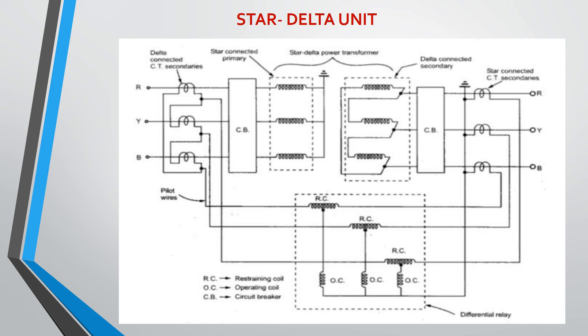The picture here depicts the differential protection technique applied to the star-delta power transformer. Star-delta means the primary side of the transformer is connected in star — you can see a neutral point — whereas the secondary side is connected in delta. To cope with the phase shift, the delta side of the power transformer must be connected to star-connected CTs, and the zero sequence current needs to be compensated with the help of delta-connected CT secondaries on the star side. These are then connected to the restraining and operating coils. Pilot wires are used in series with the restraining coils, and the combination of restraining coil and operating coil makes the differential relay.